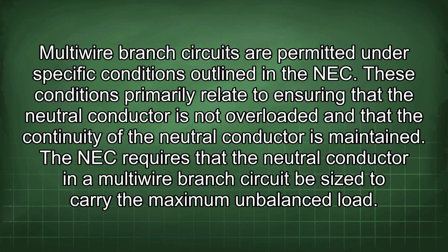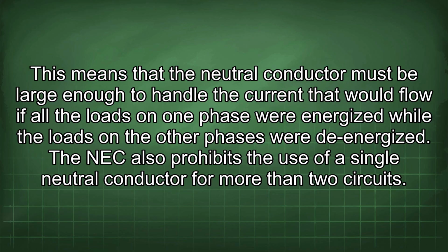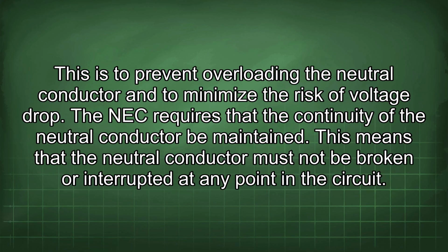These conditions primarily relate to ensuring that the neutral conductor is not overloaded and that the continuity of the neutral conductor is maintained. The NEC requires that the neutral conductor in a multi-wire branch circuit be sized to carry the maximum unbalanced load. This means that the neutral conductor must be large enough to handle the current that would flow if all the loads on one phase were energized while the loads on the other phases were de-energized. The NEC also prohibits the use of a single neutral conductor for more than two circuits. This is to prevent overloading the neutral conductor and to minimize the risk of voltage drop.